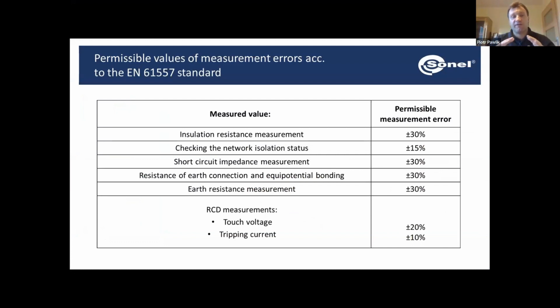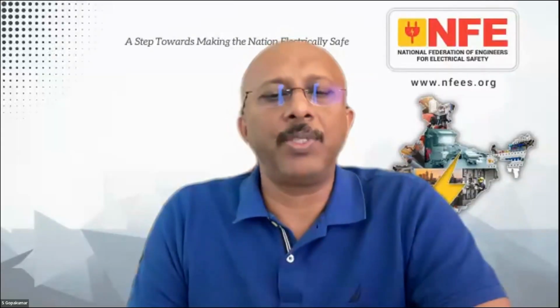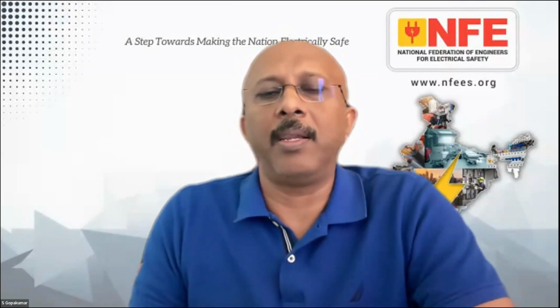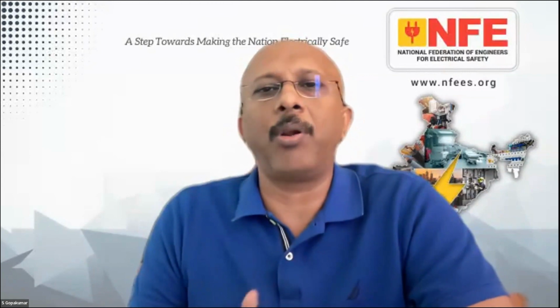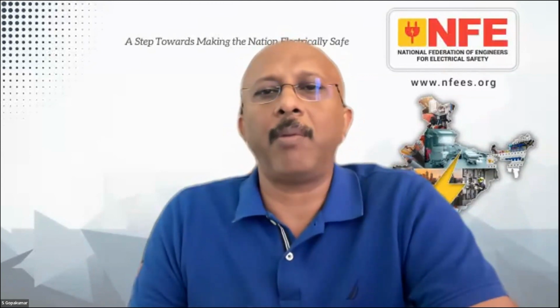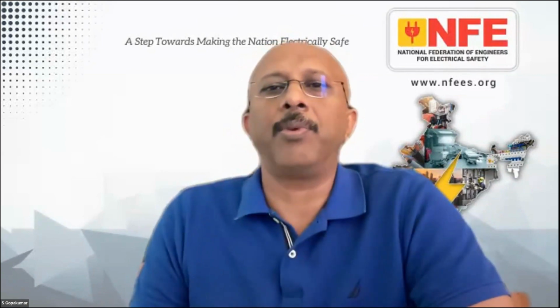Well, when we look at the low parts of the display range, then especially errors from the digits will constitute a big percentage. So here basically we have the maximum error which is described by the standard. We need to make sure that our meters comply with this. Also, in the technical specs of the meters, in their manuals, we can find the measuring ranges according to IEC 61557. Actually, these maximum allowed errors, which are given as plus or minus 30%, itself give a very good indication. Now, if you look at the standard, there are safety margins already built into the standard. As a result, even if the values are plus 30%, for example, the disconnection is ensured. That is how it works.